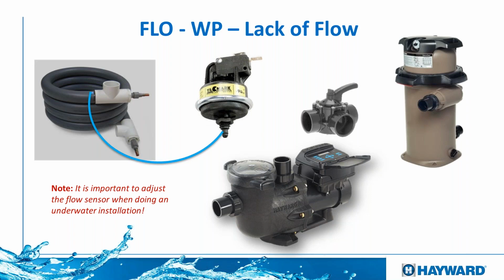Another thing, the little hose that is connected between the heat exchanger and the sensor sometimes could be clogged up with a little bit of dirt or something. So we can disconnect that little hose, then turn the pump on and make sure that the water spits out of that little hose, and then connect it back in. So again, flow, definitely look outside.